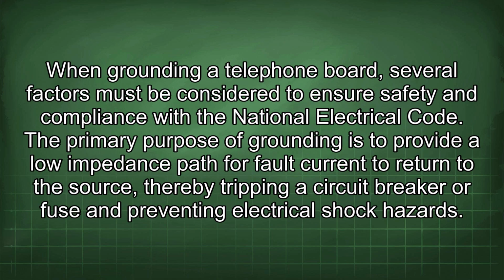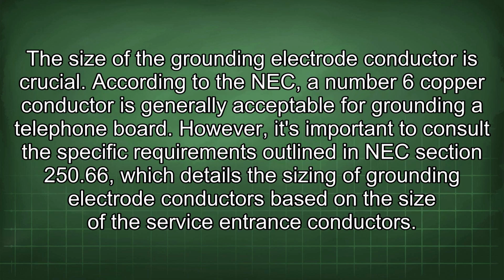When grounding a telephone board, several factors must be considered to ensure safety and compliance with the National Electrical Code. The primary purpose of grounding is to provide a low impedance path for fault current to return to the source, thereby tripping a circuit breaker or fuse and preventing electrical shock hazards. The size of the grounding electrode conductor is crucial. According to the NEC, a number 6 copper conductor is generally acceptable for grounding a telephone board.